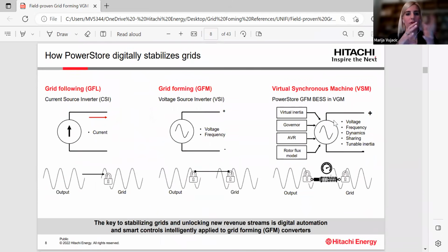As I said at the beginning of the presentation, battery energy storage system control system is multi-level. It's quite complex, and in Hitachi Energy, it consists of different control loops or control layers. But these slides represent our primary control, so it is control that is implemented at a power conversion system. So grid following is current source inverters, which operates by locking onto the grid by a mechanism called phase-locked loop, and it pushes current into the grid to provide energy as a service. This control is mostly used in the context of grid-connected systems.